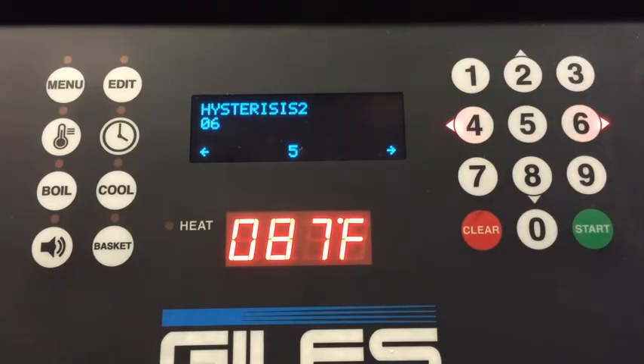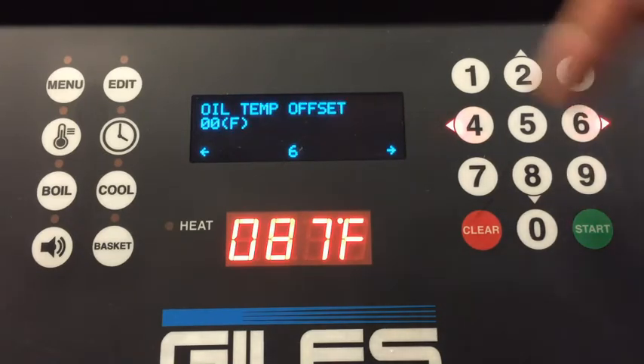Hysteresis 2, on a gas, the GGF 720 is a large gas unit. There is a secondary valve, and that one operates off that hysteresis 2. So if it continues past the 3, at 3 degrees, the primary valve will open and it'll fire up. If it continues to drop, at 6 degrees below, the second valve comes on so that it's got maximum heat, and it'll bring that heat up a little bit quicker. Both of those will drop out at set point. Oil temp offset is for calibration.